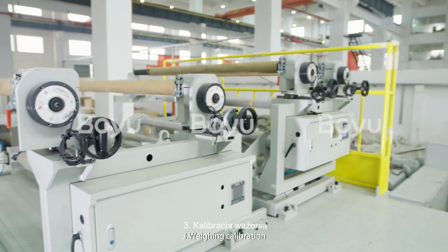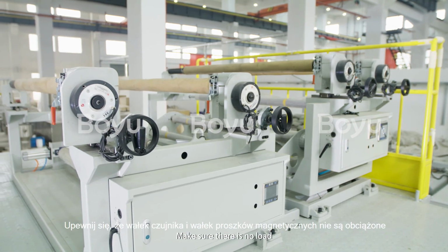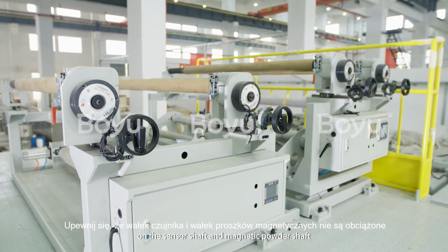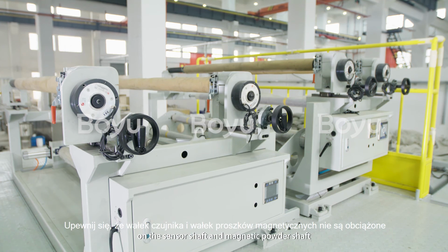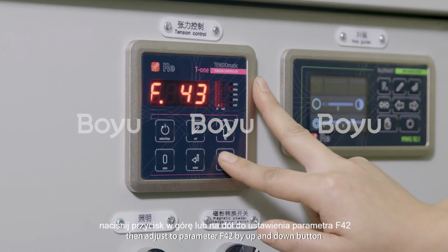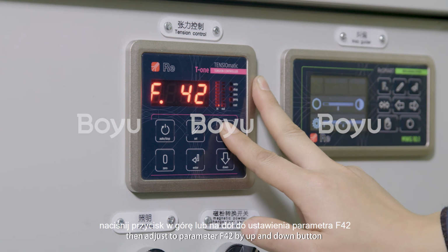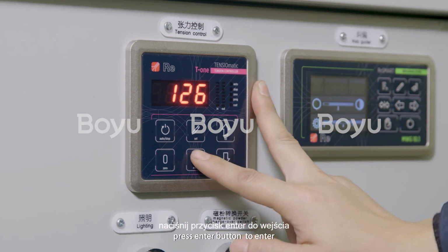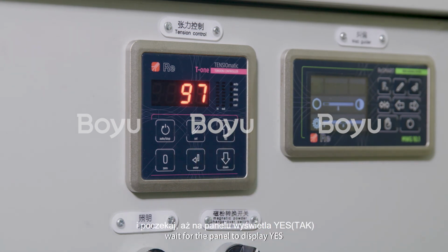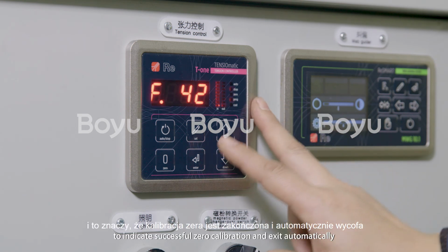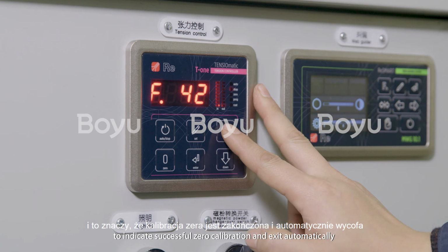3. Weighing calibration. Make sure there was no load on the sensor shaft and magnetic powder shaft. Then adjust to parameter F42 by up and down button. Press Enter button to enter. Wait for the panel to display Yes to indicate successful 0 calibration and exit automatically.